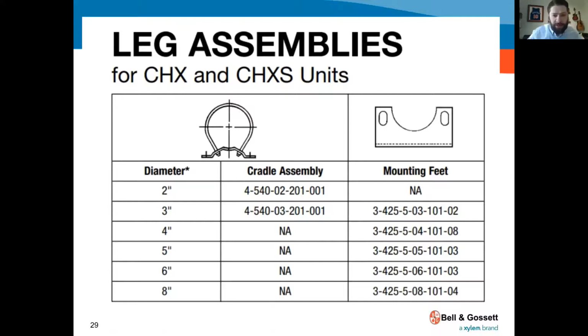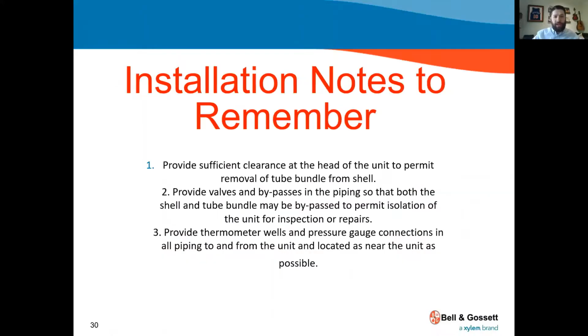I don't know why they don't sell them in pairs, because you always use 2, no matter what you're using, but you do need 2 per unit. Okay, installation notes to remember. Provide sufficient clearance of the head so you can remove the tube bundle. So for any maintenance on this unit, if it's a gasket or if you need to replace a tube bundle, anything like that, you need to pull that thing out. So make sure you leave proper clearances, and I'll show you where to find your proper clearances in a moment.